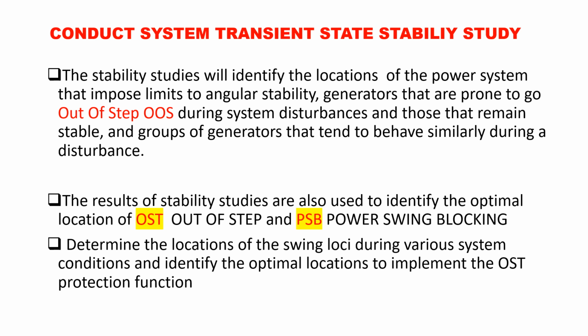If the delta angle increases beyond a certain limit, then the generator cannot come back into synchronism automatically. That is known as the unstable power swing, and the system goes into instability, and ultimately there is an out of synchronism tripping of the generators, and you will see blackouts and the breakdown of the power system.